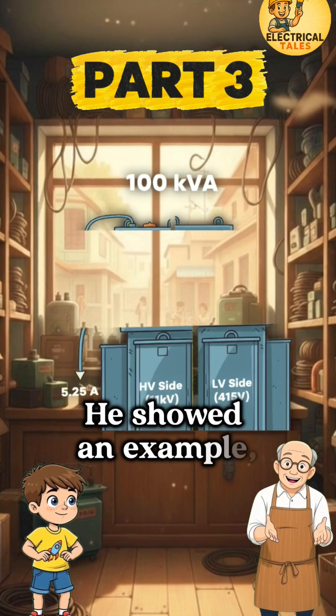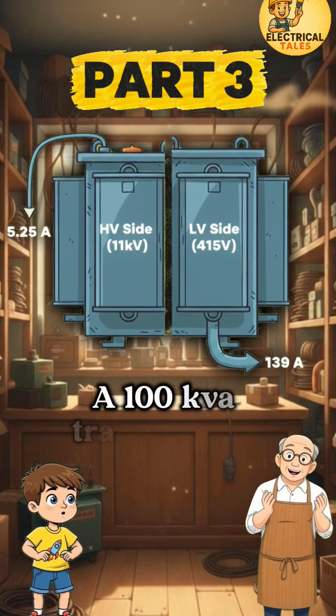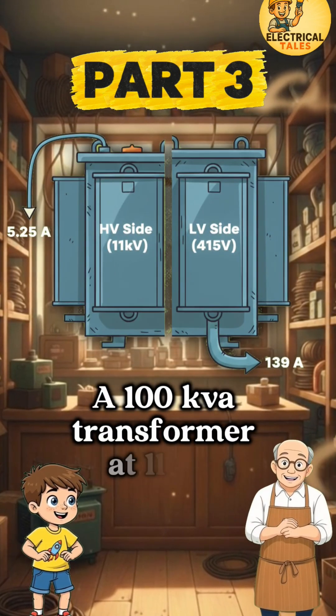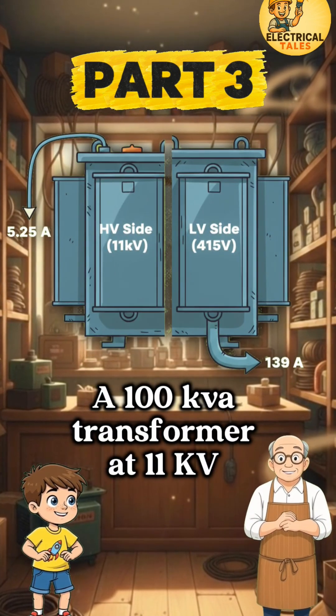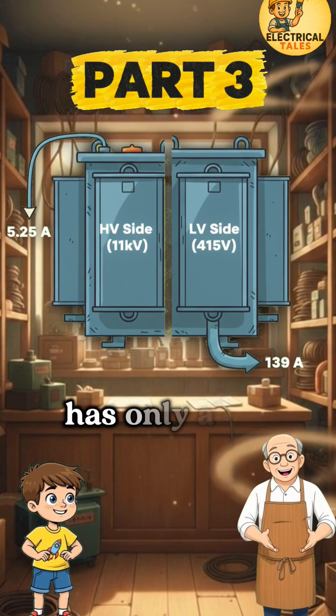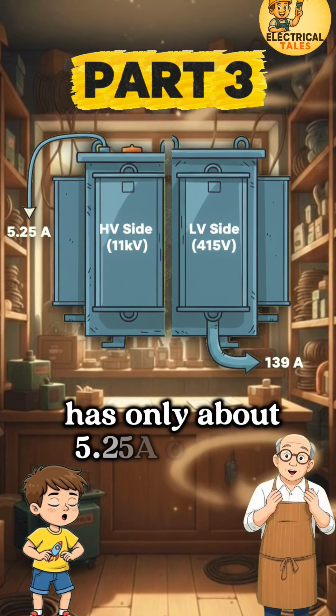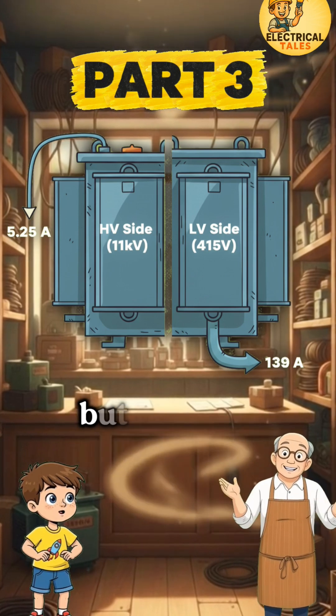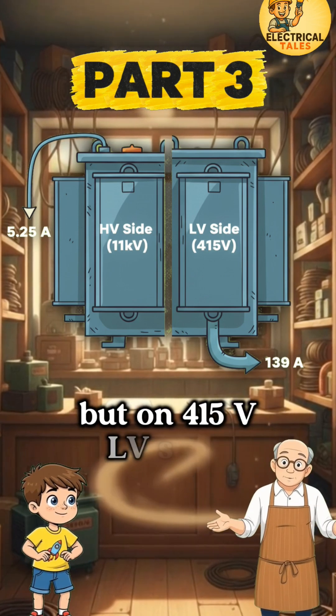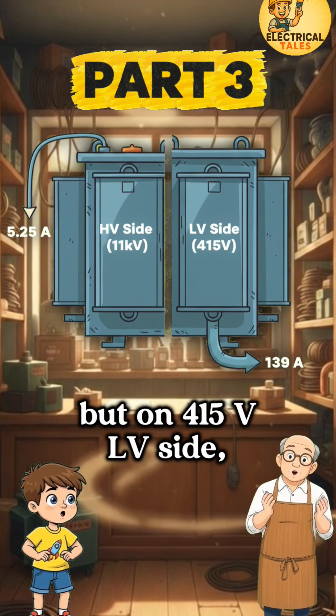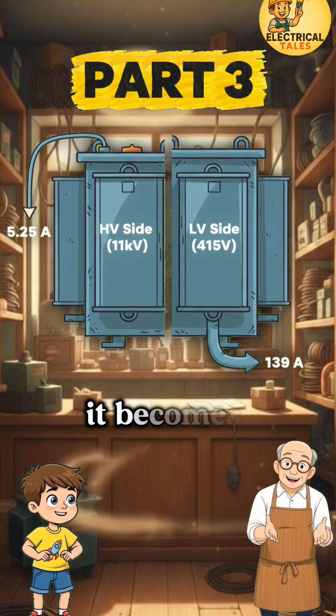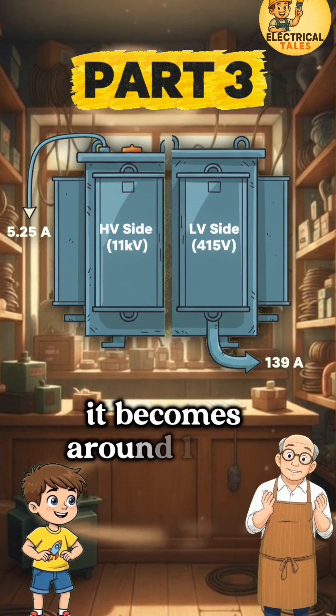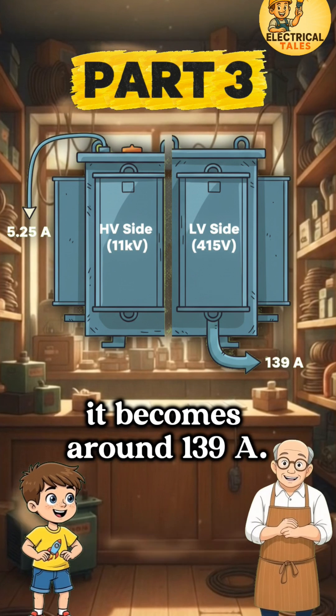He showed an example: a 100 KVA transformer at 11 KV has only about 5.25 A on the HV side, but on the 415 V LV side, it becomes around 139 A.